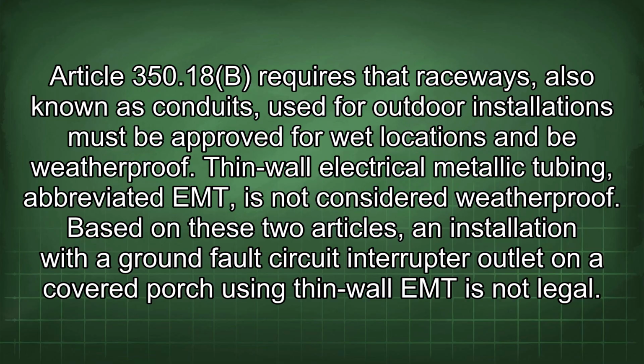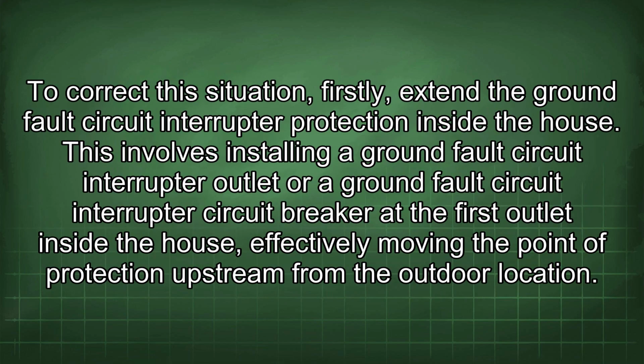Based on these two articles, an installation with a ground fault circuit interrupter outlet on a covered porch using thin wall EMT is not legal. To correct this situation, firstly, extend the ground fault circuit interrupter protection inside the house. This involves installing a ground fault circuit interrupter outlet or a ground fault circuit interrupter circuit breaker at the first outlet inside the house, effectively moving the point of protection upstream from the outdoor location.